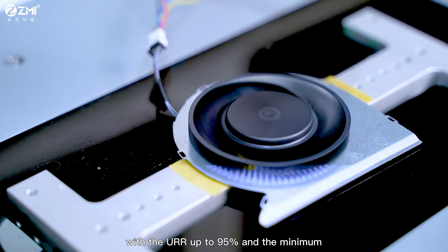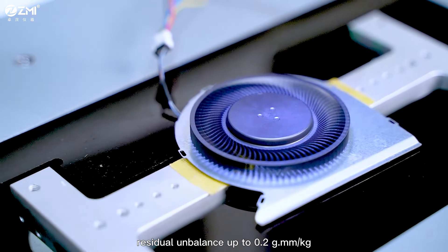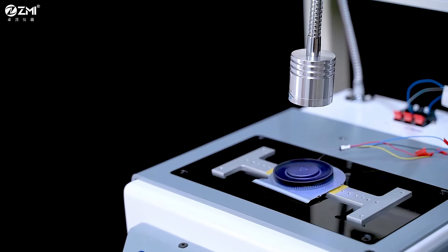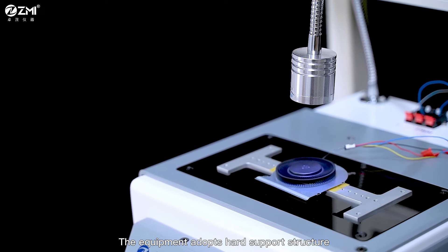The balance effect is remarkable, with the URR up to 95%, and the minimum residual unbalance up to 0.2 gram millimetres per kg. The unbalance interference ratio is less than 2%.